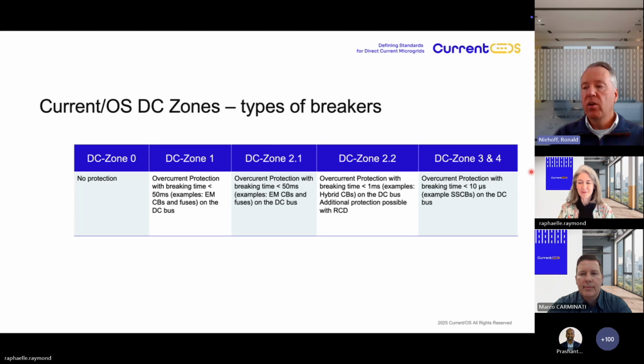Within the zone 3, there are all types of grid architectures possible, as already said, with combined multiple sources and loads on one cable, and fault protection and protection against direct and indirect touch is guaranteed with bringing all the benefits of DC together. And therefore I close my part of this webinar to say that I'm absolutely believing that safety on DC prosumer electrical installation is at least on the same level as what we already used to in AC prosumer electrical installations.